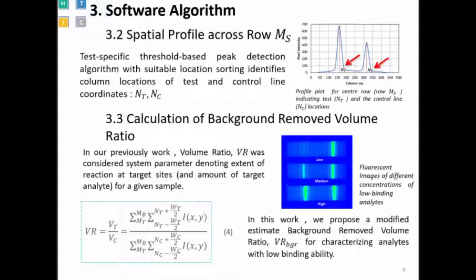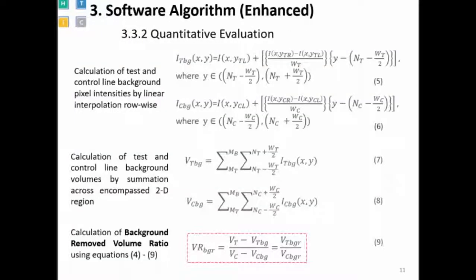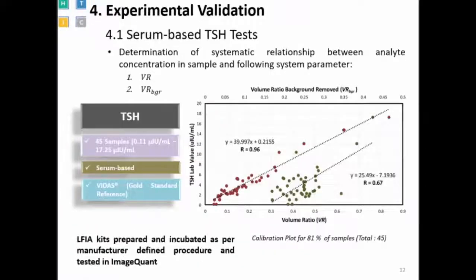The new VR equation subtracts a constant background portion from both test and control lines, which improves the final dynamic range of the output. We tested this on TSH, which typically suffers from a lower sensitivity range. With the original VR, we achieved an R of 0.67, and with the background-subtracted VR we achieved an R of 0.96. This was measured across 45 different samples collected from external laboratories.